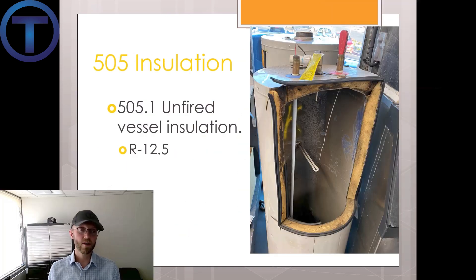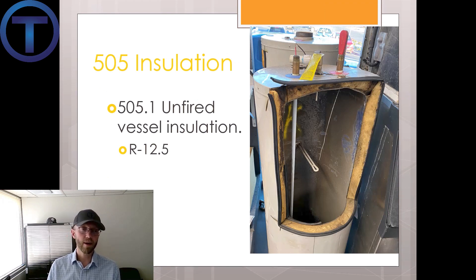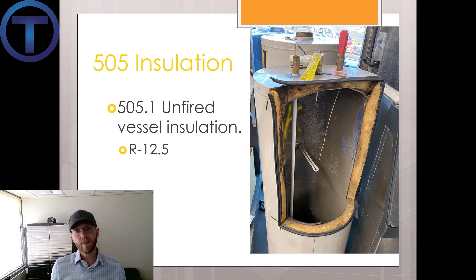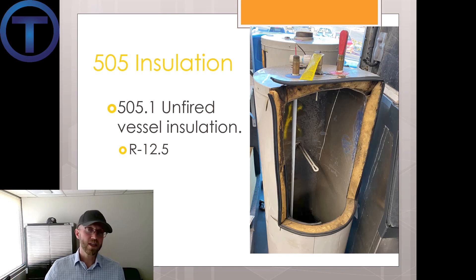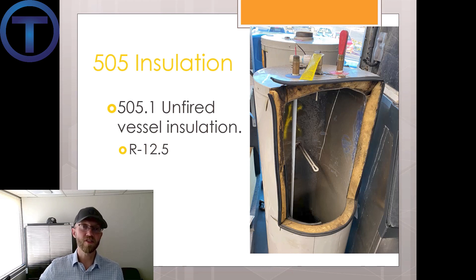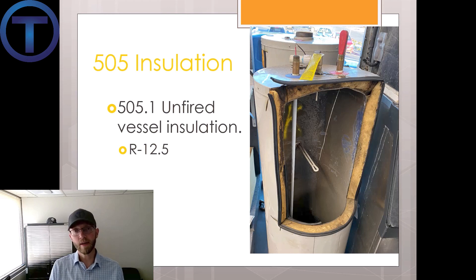Finally, section 505 talks about insulation. 505.1 covers unfired vessel insulation — an unfired vessel would be a storage tank. An electric water heater has insulation around it, as shown here. A holding tank does need to have some insulation so we don't let all the heat pass through the tank into the room and lose that energy. R-12.5 is the minimum insulation value required for such a storage tank.